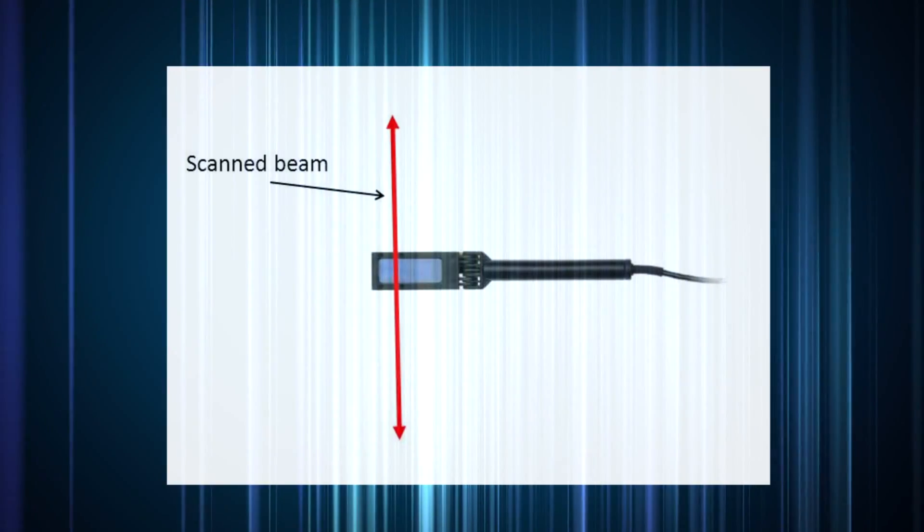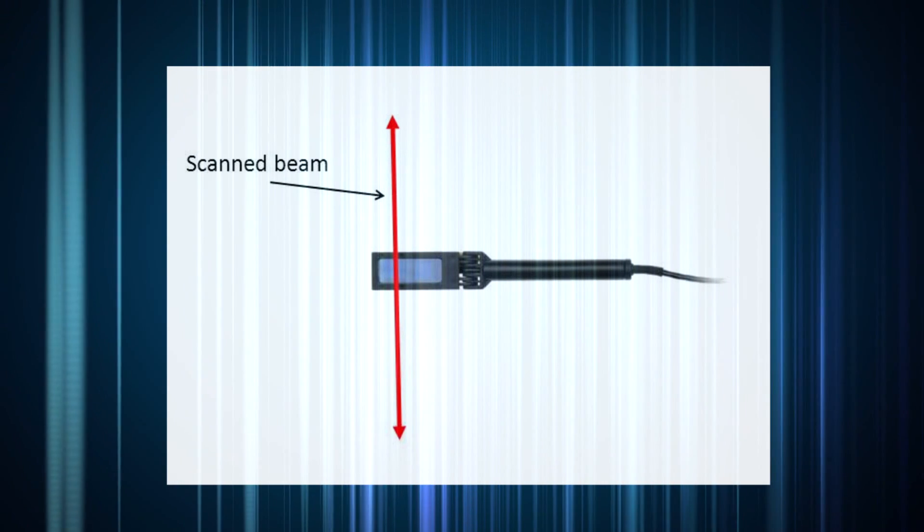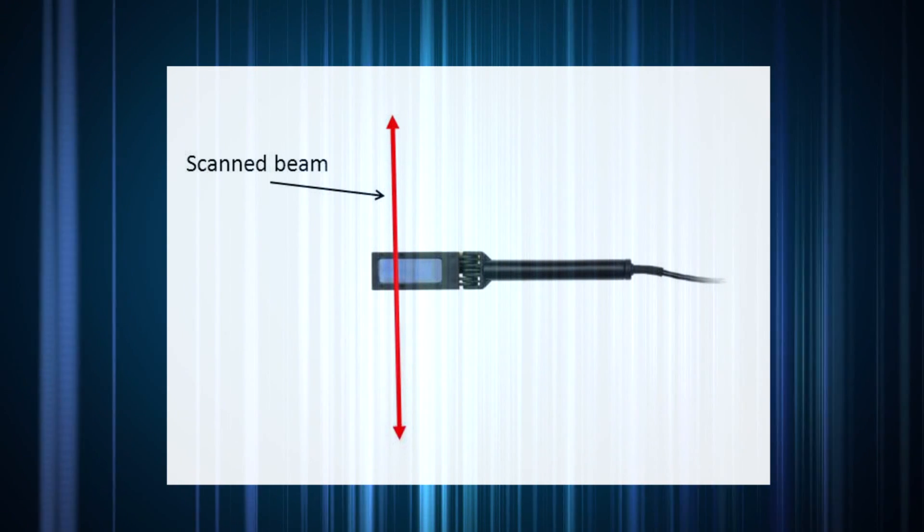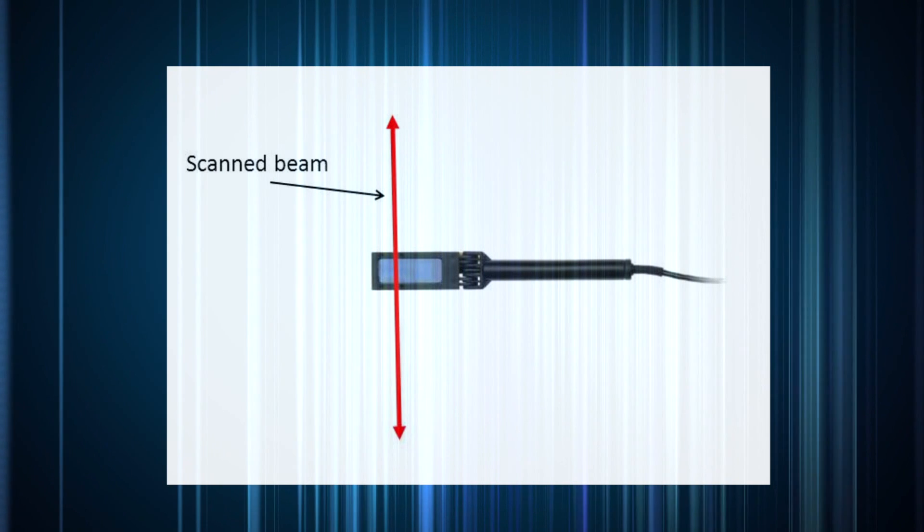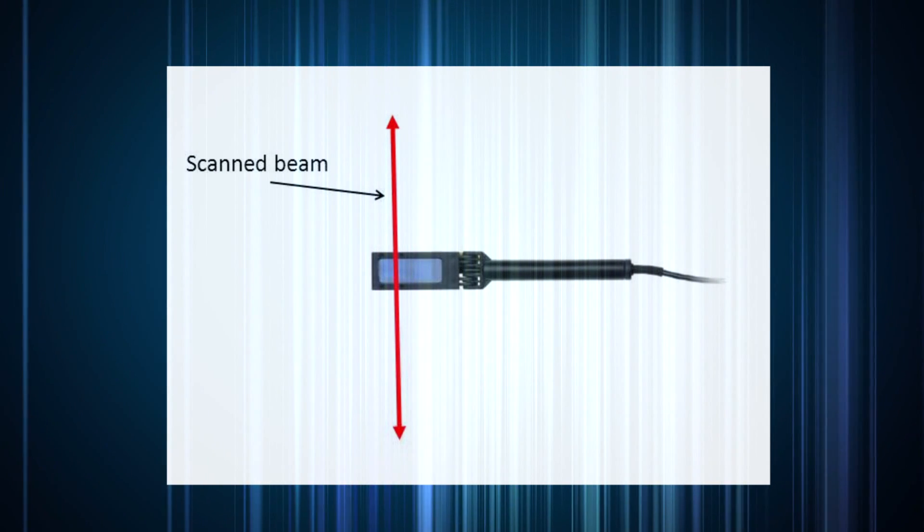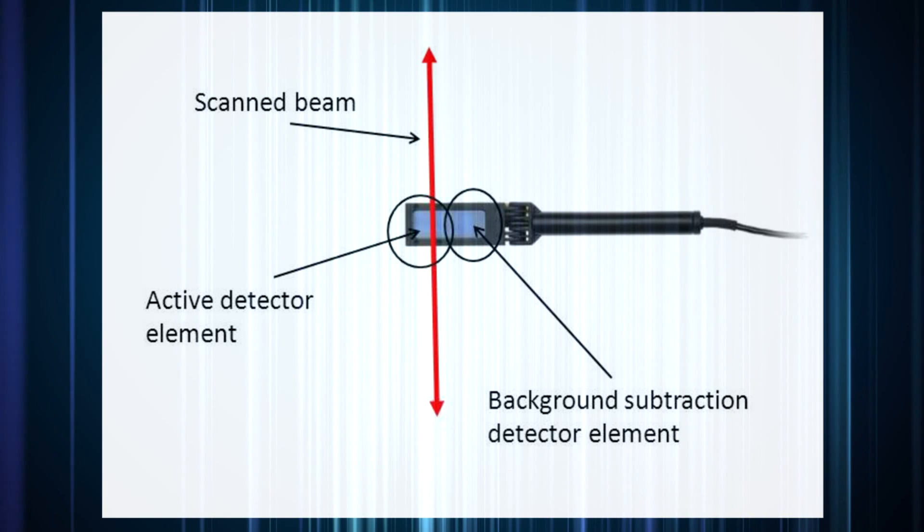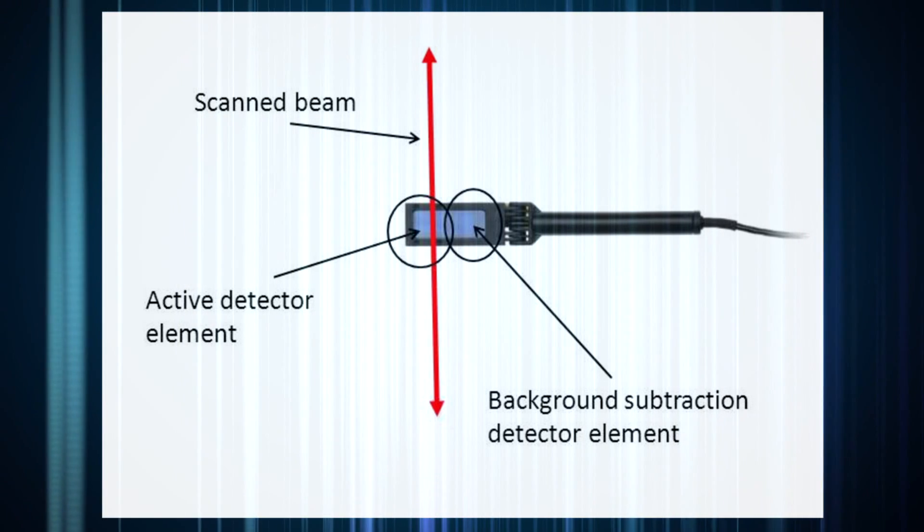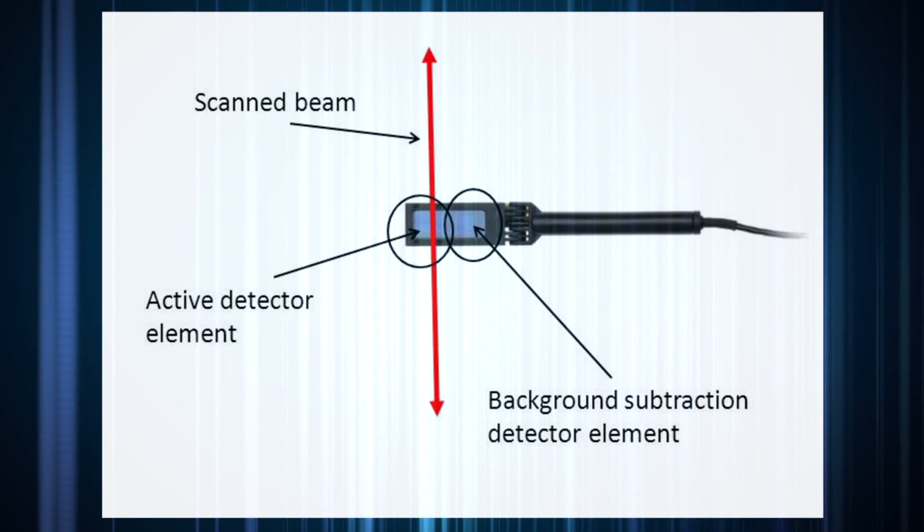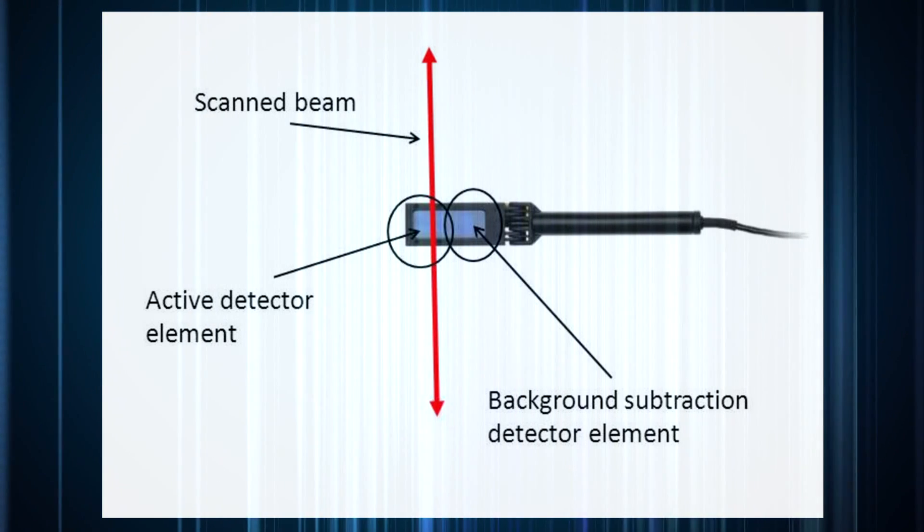Here's how it's used. The beam is scanned across the outer detector element as shown here. The inner detector provides background light subtraction. You choose the wavelength setting and power scale as for any standard photodiode-based power sensor, and you measure.